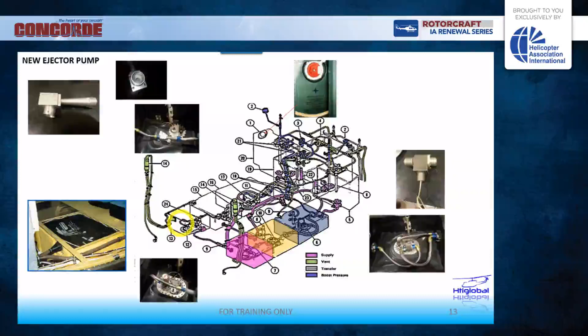These transfer pumps, as well as the boost pump, are energized with 28 volts DC, and these are what we call positive displacement pumps. When you turn this pump on, it supplies all the pressure and flow of fuel it can. There's no control, it's just on and off.